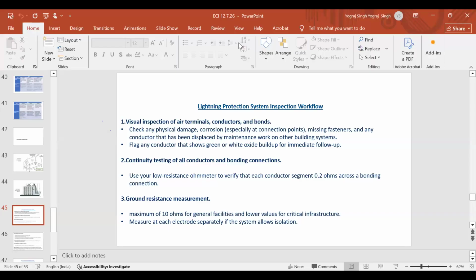So continuity of all the conductors is very important. One conductor will not continue throughout the length, because there will definitely be joints somewhere. So the resistance should not be more than 0.2 wherever this bonding connection has been made. Now ground resistance will not be more than 10 ohm. What we are showing here, this earthing resistance will not be more than 10 ohm. Otherwise, normally whatever earthings we provide, they provide 5 ohm.